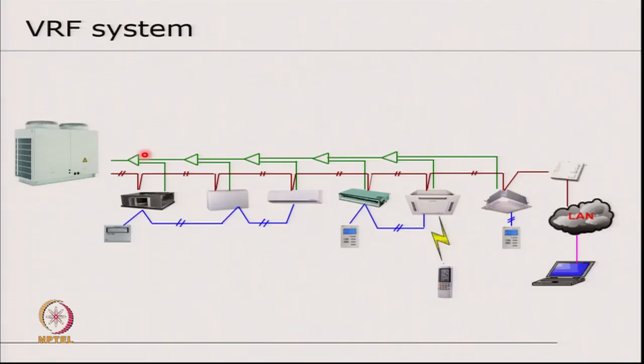If you look at just the systems, this is what an outdoor unit would look like, and the outdoor unit is then connected to several indoor units, both through the refrigerant piping and also through the controls. And if you look at the complexity, we need to know what the cooling demand is in each of these indoor units. It needs to be consolidated at one point, and then determine what compressor speed should be operated to address that cooling demand.